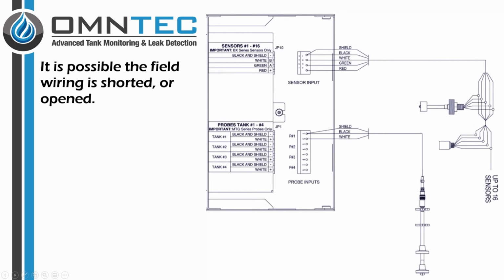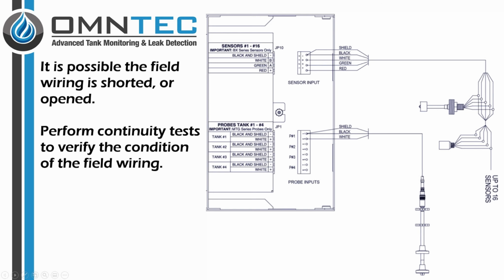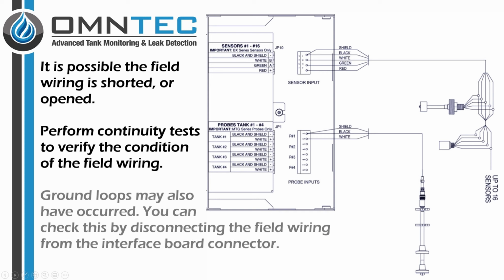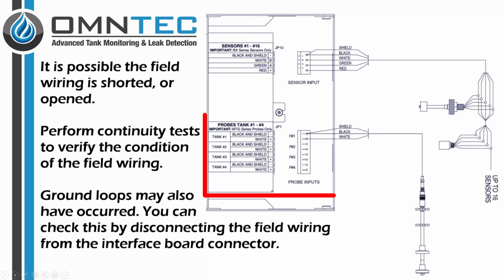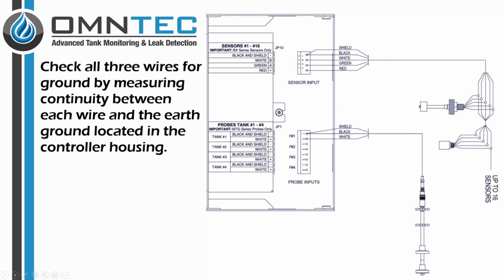It is possible the field wiring is shorted or opened. Perform continuity tests to verify the condition of the field wiring. Ground loops may also have occurred. You can check this by disconnecting the field wiring from the interface board connector. Check all 3 wires for ground by measuring continuity between each wire and the earth ground, located in the controller housing.